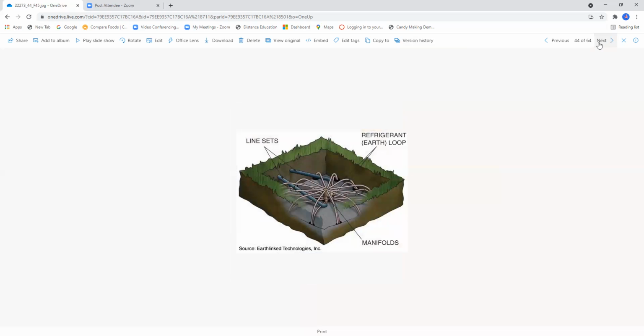Okay, here we have the situation on page 1348, and this would be figure 44.45. It shows the earth loop manifold right here. So basically, notice that you got your piping come in, and then you got what you call your spider works right here. Notice all your connections are made in a vault type arrangement where they're accessible in the event that we have leaks. These are your earth loops that are direct burial. And then of course, this is your line sets that go to the heat pump unit.